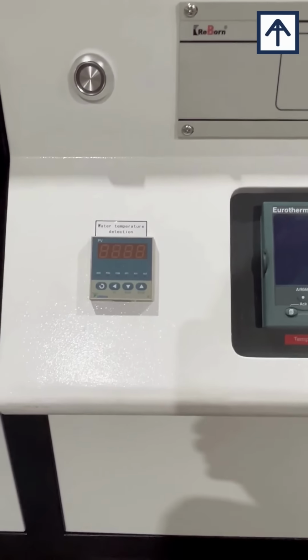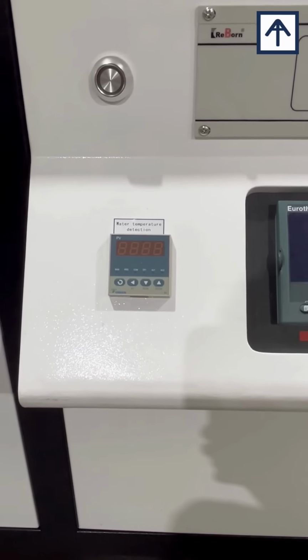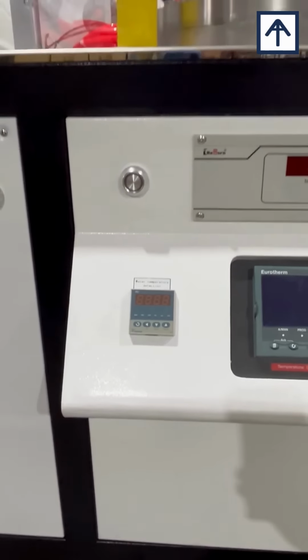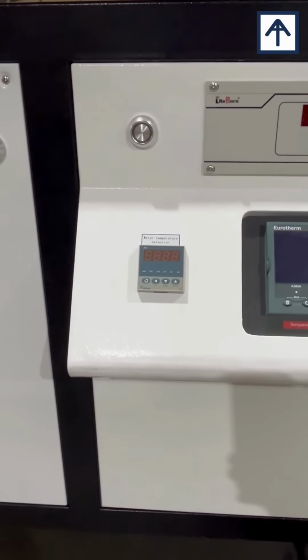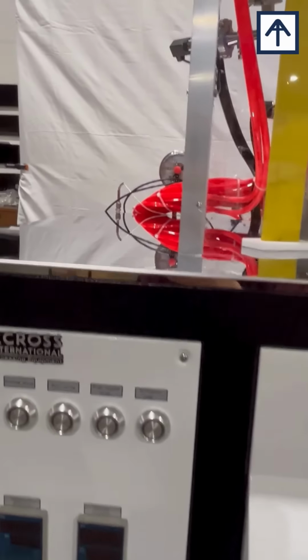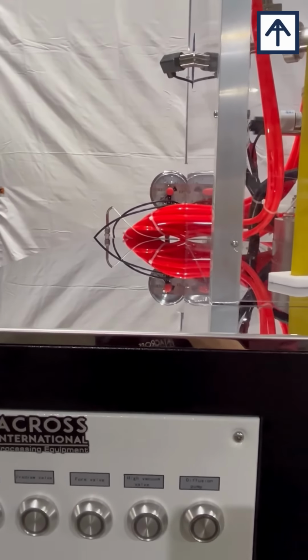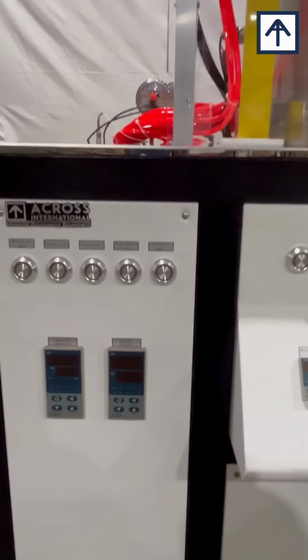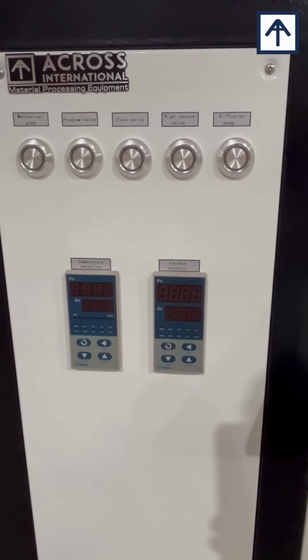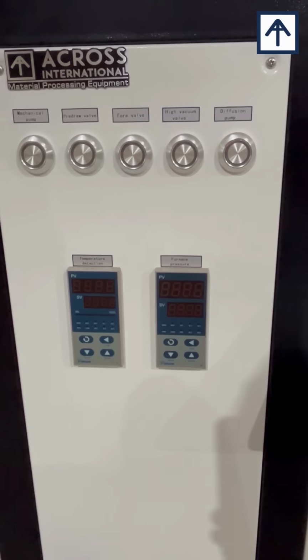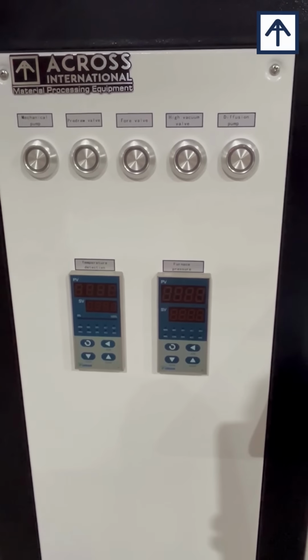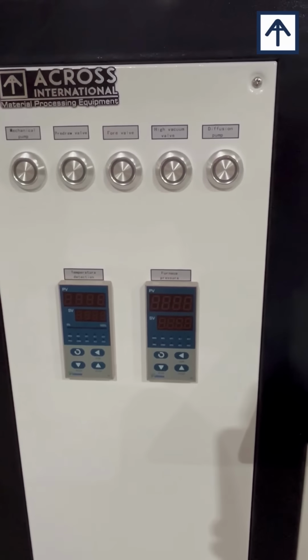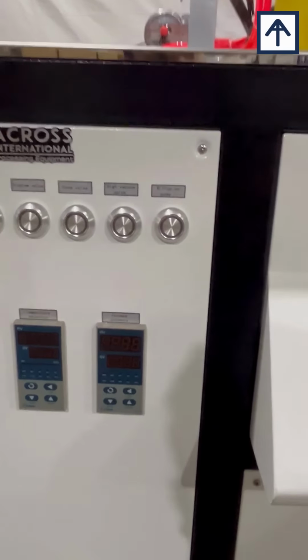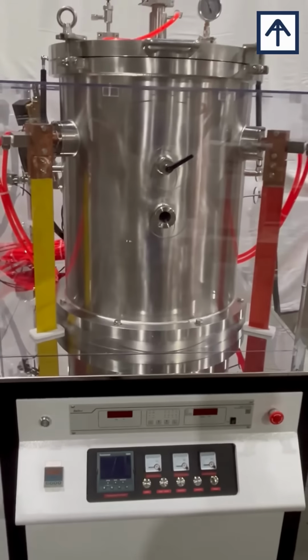And then you also have the water temperature detection, which lets you know the water temperature of the insulation jacket, and it's set to like 10 degrees Celsius. So if your chiller fails, the water temperature sensor detects it, and if the pump on the chiller fails, it's the pressure sensor that will turn off the unit as well. And then you also have your furnace pressure, the chamber pressure that it detects on there. And then you also have the mechanical pump switches, the pre-draw valve and the foreline valve and high vacuum valve, as well as the diffusion pump valves. So these are the key features on the unit.